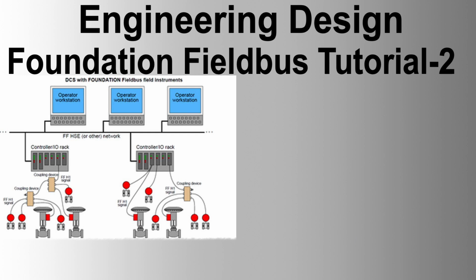Virtual Field Device, VFD. A Fieldbus device may have user applications which are independent of each other and do not interact. A Fieldbus device consists of virtual field devices for such individual applications. An identifier given to a VCR identifies the VFD. A Foundation device has at least 2 VFDs. One is the management VFD where network and system management applications reside, and the other is a function block VFD where function blocks exist.